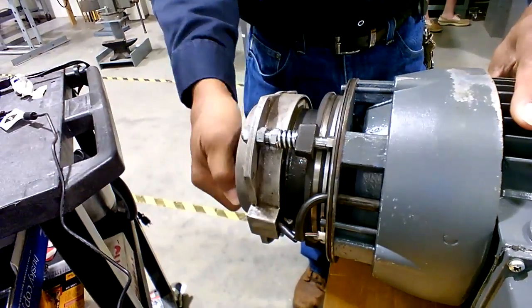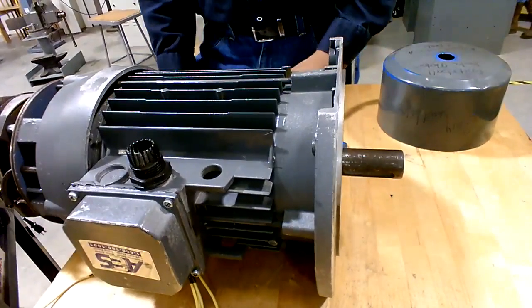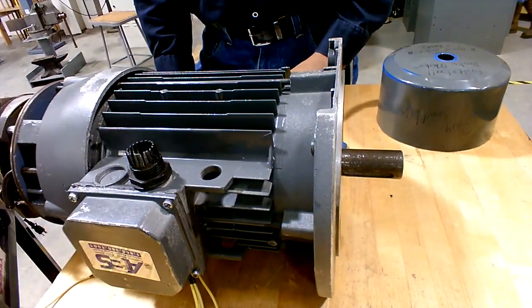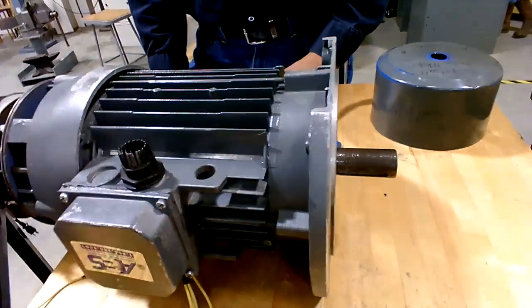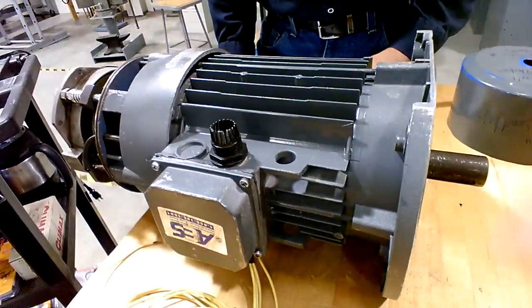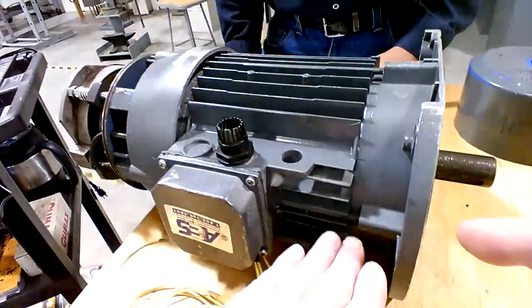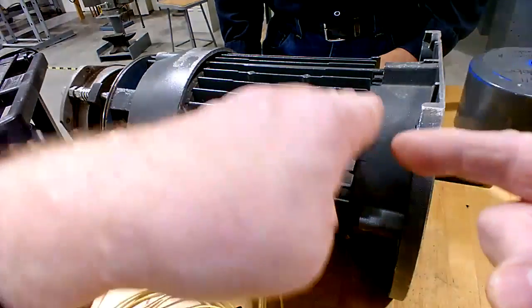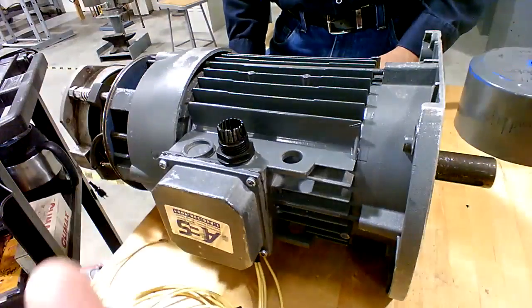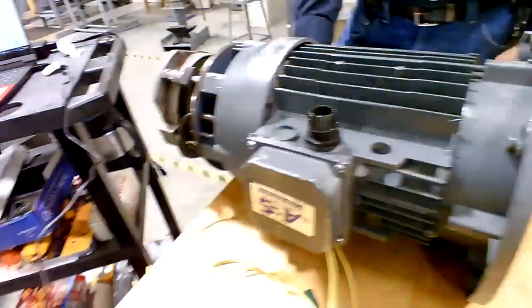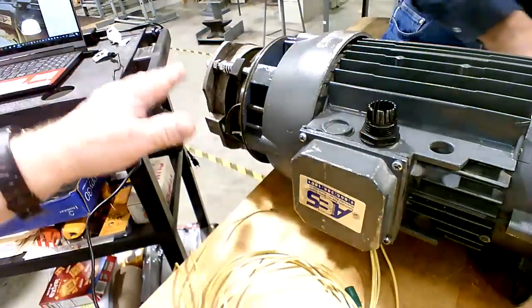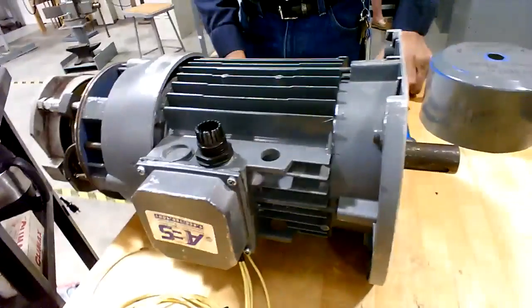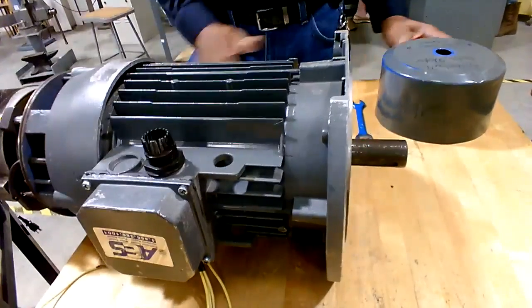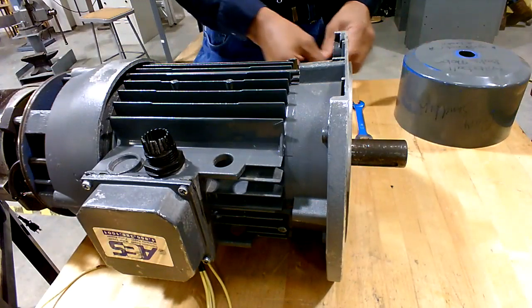Servos operate electrically by stopping things very quickly. But this would be the next thing under kind of a servo. You don't know the position of it. The way you know the position to stop something would be with an external sensor. And if you have a plate that this thing is controlling, when it gets up to the sensor, the PLC would in turn turn a starter off, it would de-energize, and it would block this. It kind of gives you a roundabout way of having a good precise position.